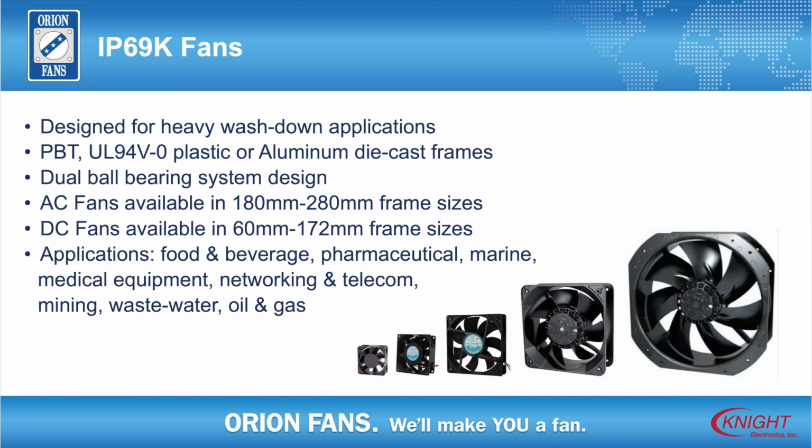and water ingress. This rating is designed to provide the maximum environmental protection to electronics that are expected to work under the harshest of conditions. The IP69K rated fans are protected against high pressure up to 1,450 psi, high temperature 80 degrees Celsius, washdown spraying from less than 4 inches away at various angles for a minimum of 30 seconds at each angle, and a flow rate of 14 to 16 liters per minute.